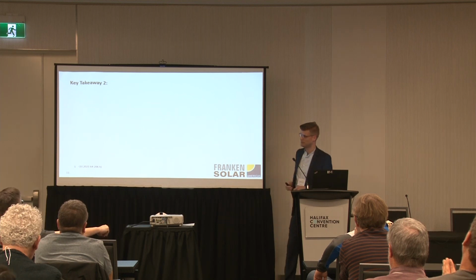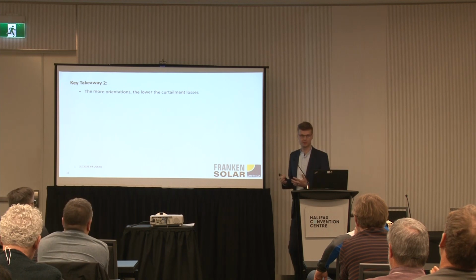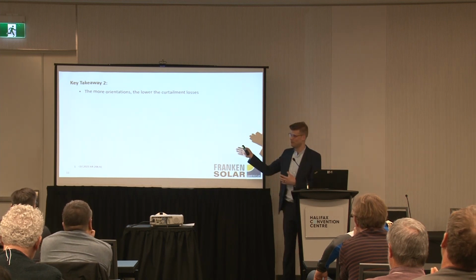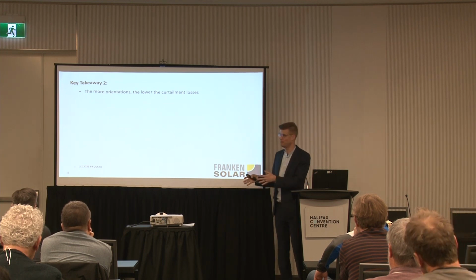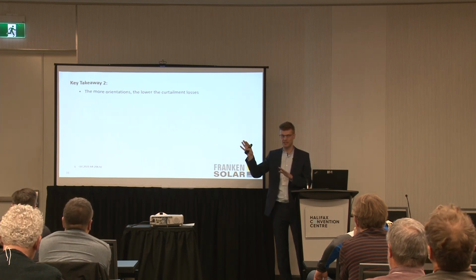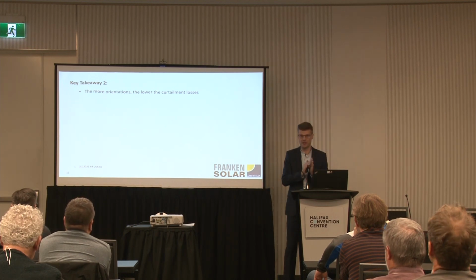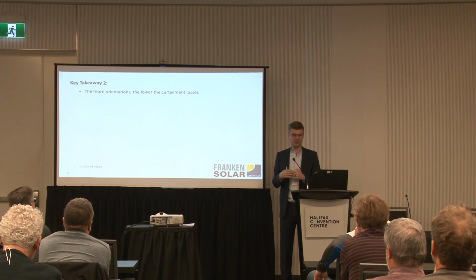When we look into a summary, the more orientations you have from an oversizing perspective, the better it is because you have less curtailment. For example, if you have two sides and you have 50% of the solar system on one and 50% on the other, it makes sense that in case of two inverters, you always have one string from the east side and one string of the west side on the same inverter, because otherwise you're not utilizing that smooth curve where you have less curtailment losses.